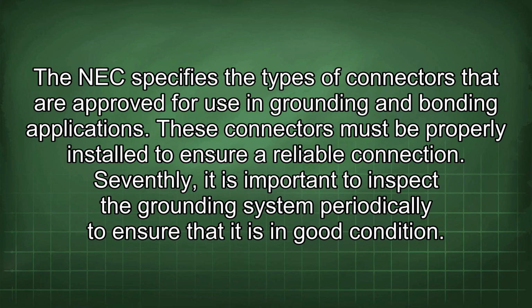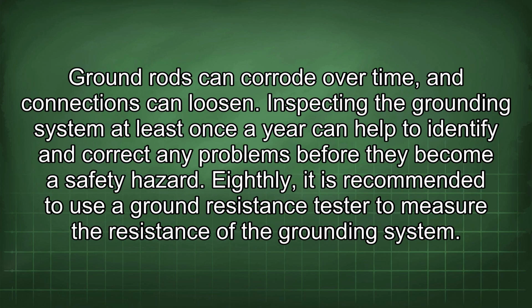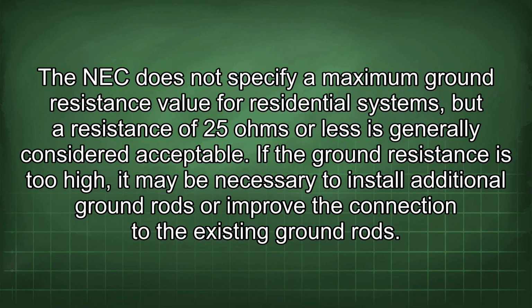Seventhly, it is important to inspect the grounding system periodically to ensure that it is in good condition. Ground rods can corrode over time and connections can loosen. Inspecting the grounding system at least once a year can help to identify and correct any problems before they become a safety hazard. Eighthly, it is recommended to use a ground resistance tester to measure the resistance of the grounding system. The NEC does not specify a maximum ground resistance value for residential systems, but a resistance of 25 ohms or less is generally considered acceptable.